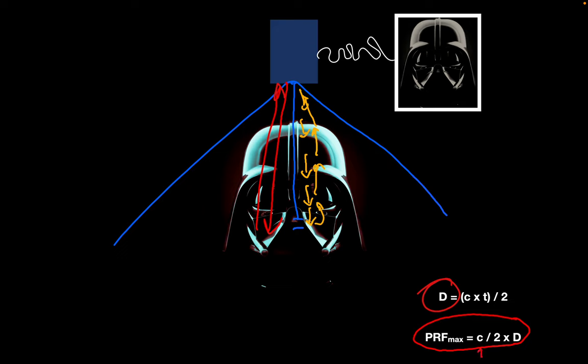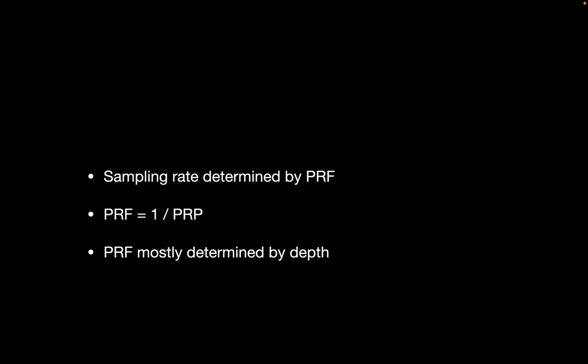Since the velocity of ultrasound in tissues is 1540 meters per second — a given — the pulse repetition frequency will be determined by imaging depth. The sampling rate is determined by the pulse repetition frequency, and pulse repetition frequency is determined by the pulse repetition period, which is governed by how deep you place your sample volume.